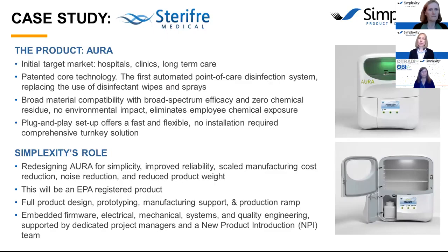So right now, let's say you're a doctor and you use a stethoscope, or the nurse puts a blood pressure cuff on someone. The current standard is disinfecting sprays and wipes, and there are a lot of problems, and there's a lot on their website as to what the problems are with that in terms of chemical exposure, how well something is wiped, is it really disinfected, and so forth. And so they've developed this device called Aura, which is a box that's mounted on the wall, and then the medical personnel can put the stethoscope or other items, even electronics, into the device, and it disinfects it. And what's unique about Aura is that it doesn't use UV, which is line of sight. So with UV, it only would disinfect the area that the UV can see. This uses a hydrogen peroxide and ozone combination, their proprietary system, to encompass whatever is inside the box and disinfect it.